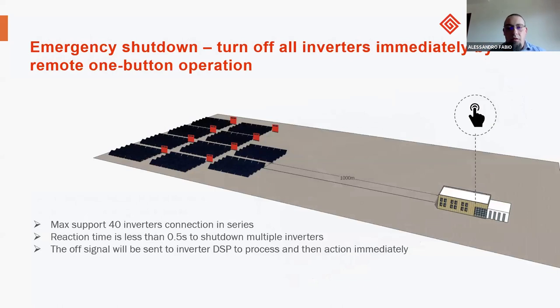Another functionality that we have is the emergency shutdown, for example for safety, so fire safety or anything like that. You have the possibility to switch off the whole system completely with the emergency shutdown. This is not optional, it's integrated in all our inverters. The maximum number of inverters you can put in series is 40, and the reaction time is 0.5 seconds, so we are talking about 500 milliseconds for all inverters, because all this technology is integrated with a separate DSP.